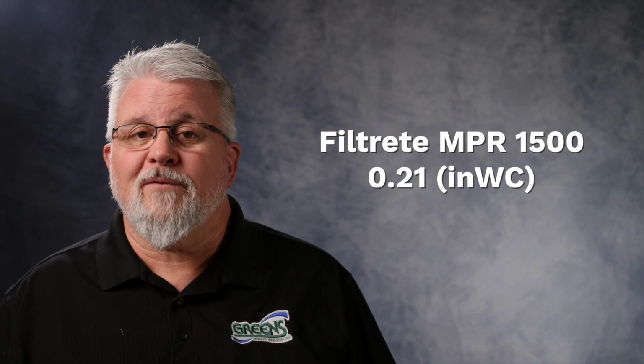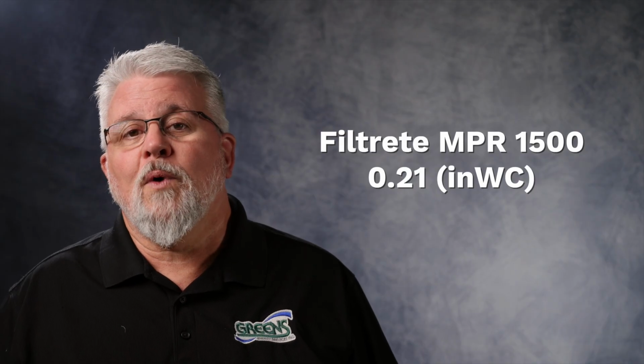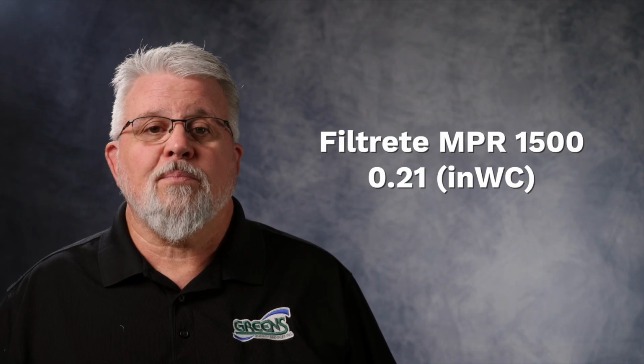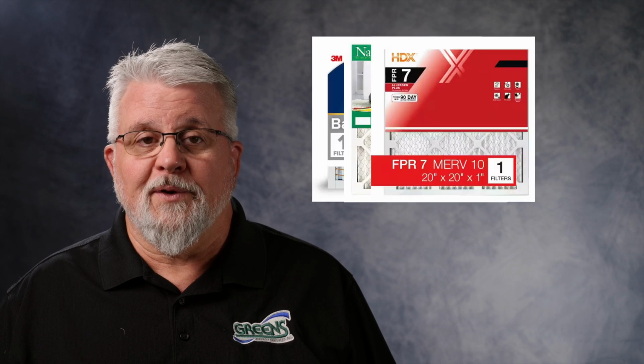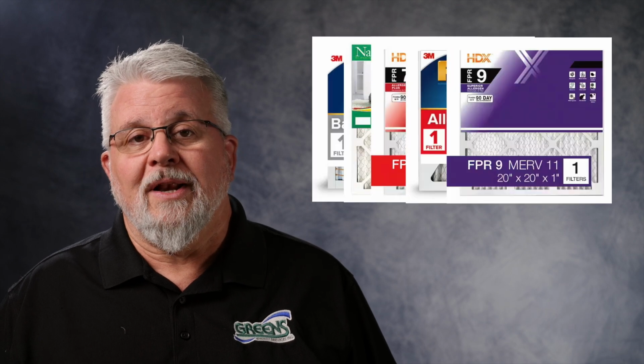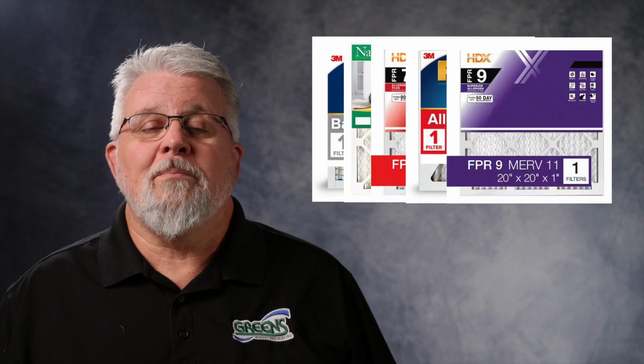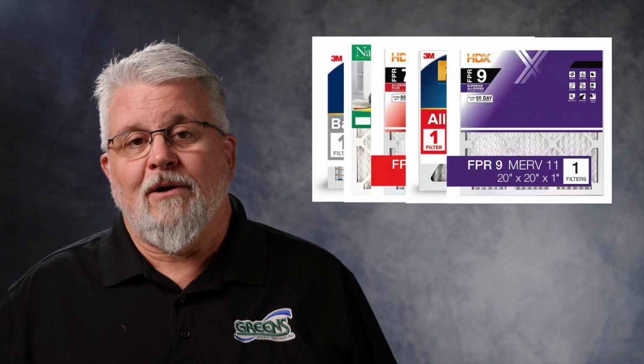That means significantly more surface area for air to pass through. And the result? The pressure drop of just 0.21 inches. Think about that for a second. This MERV 12 filter actually outperforms several lower rated filters in airflow restriction. And that was probably the single biggest surprise of the entire test.